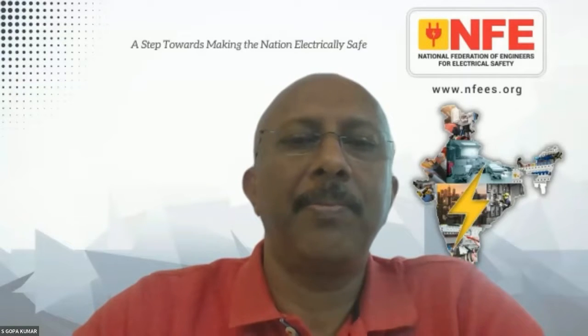And another thing which I have seen in the local bodies who give the permission of the building for occupancy, they just mention that provisions should be as per the National Building Code. But if you see their formats of giving occupancy certificates and checklist, I think the electrical part is almost negligible in any of their formats. There are a few points regarding the transformer substation, but regarding internal wiring by the electrical inspector, no points are included. So NBC so far was not mandatory. Now it's a good thing that it has been brought into this regulatory part of the electrical regulations also.